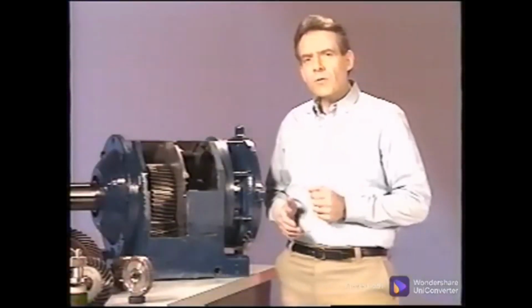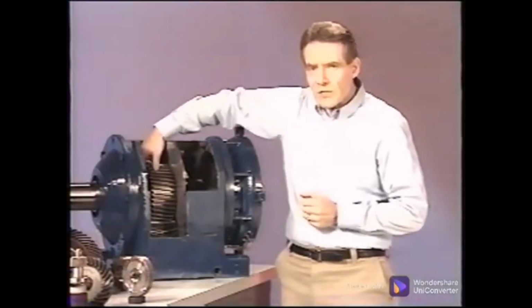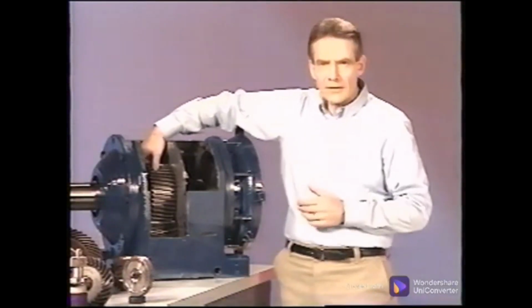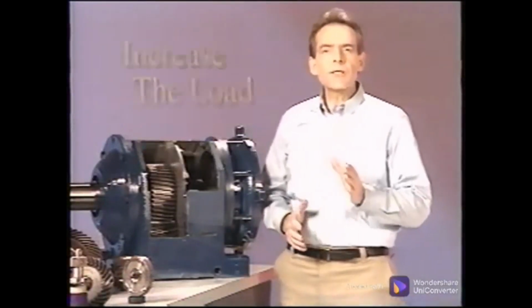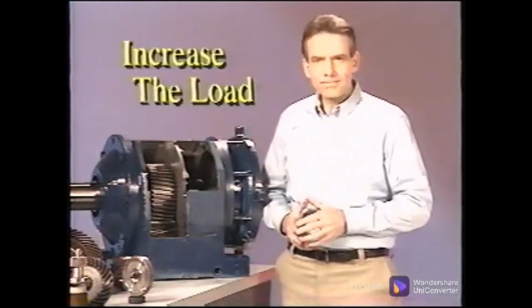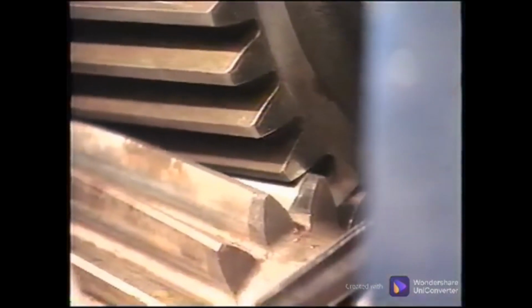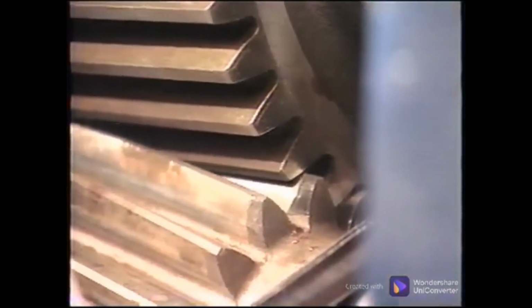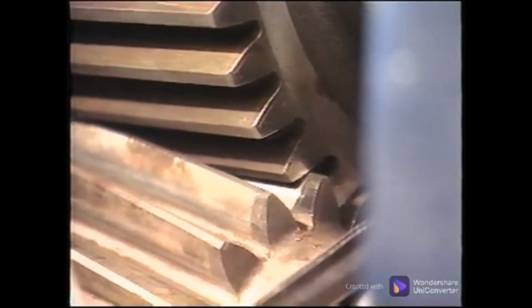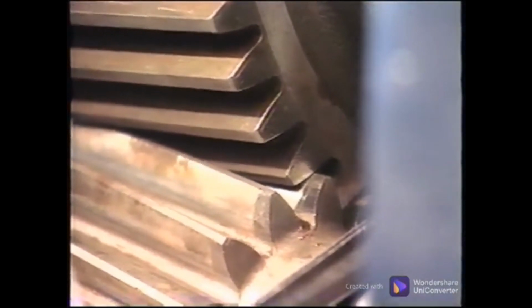When a gear train is running with no load, the teeth can slip back and forth, impacting each other. A cure for this is simply to increase the load of the machine. The hitting on the back side of the teeth means 2 impacts are made for each tooth and will result in a 2 times gear mesh frequency.